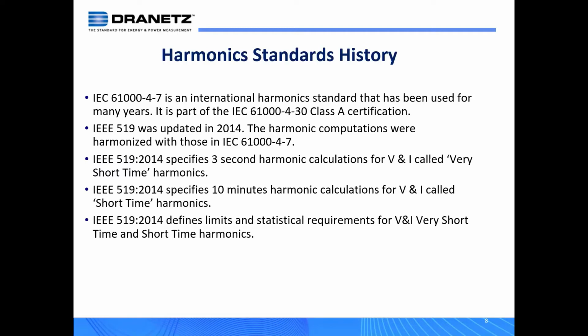So in addition to the measurement methods used for harmonics from the IEC 61000-4-7, IEEE 519/2014 added two important parameters and how to measure for the presence of harmonics. And this is in addition to the compliance limits and other things that were defined in 519/2014. And the first parameter is called very short time harmonics.